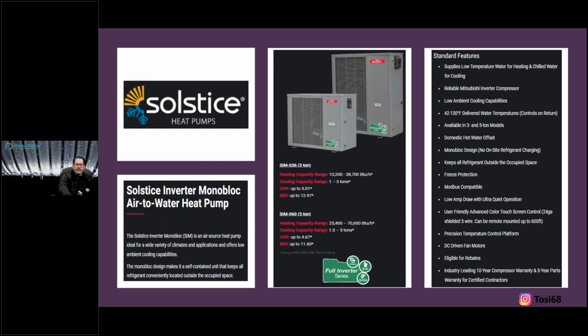We need to dive a little deeper, right? When reading this stuff, it might sound like, wow, all right, now I'm in because I can do 70,600 BTUs. Understanding what that asterisk represents, right? There was a test to prove that we can do that. What were the test parameters? What was the indoor temperature? What was the flow rate? What was the outdoor temperature? These are those deeper dives that we're going to need to do.